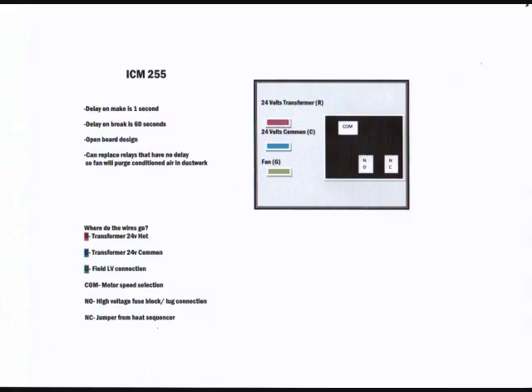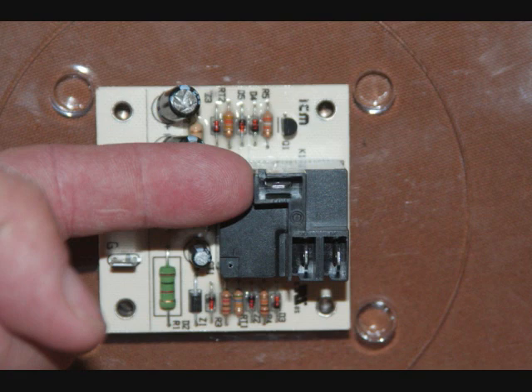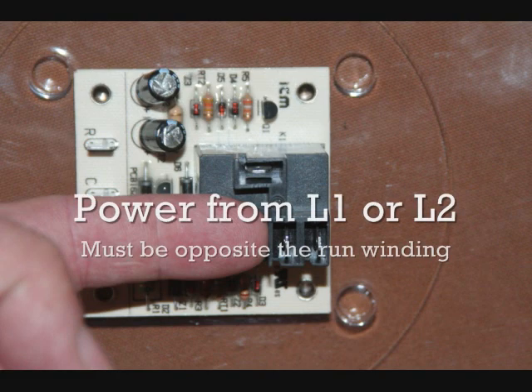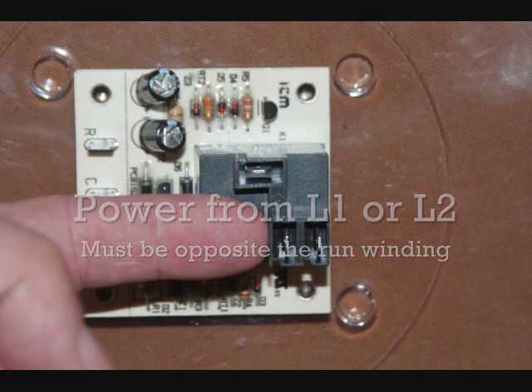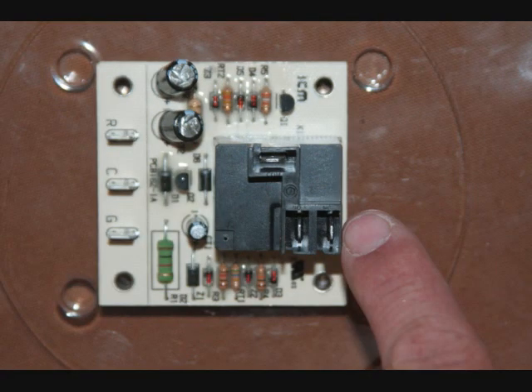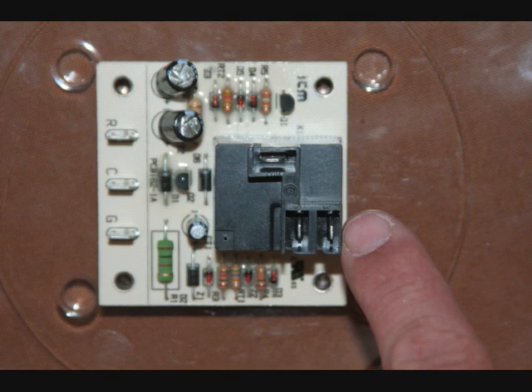The last thing is the high voltage and you'll see common, normally open, and normally closed. Your common wire will be your blower speed and it is located right here. And the next one down will be your power coming in from the lugs or wherever. And your other one will be your heat strip wire jumper from the sequencer.